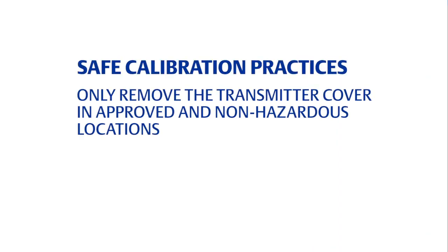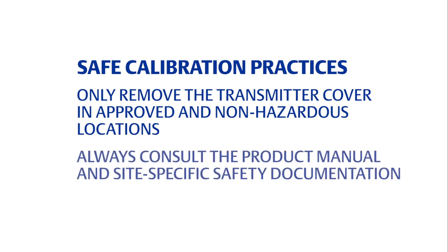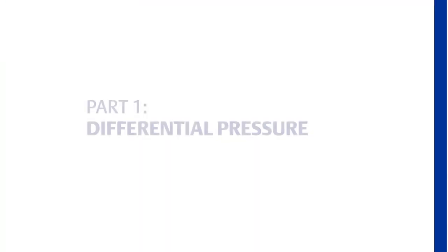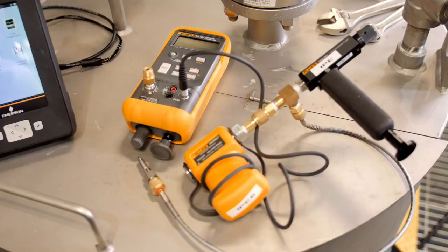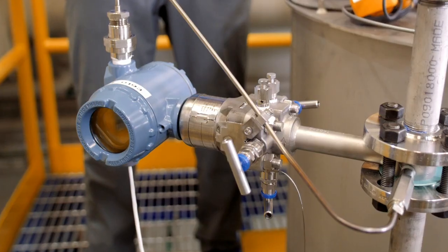Calibration and configuration should always be performed safely, and users should only remove the transmitter cover in approved and non-hazardous locations. Before beginning, always consult the product manual and your site's specific safety documentation. The tools we'll be using today are a Trex, an accurate pressure source, and a multivariable flow meter.